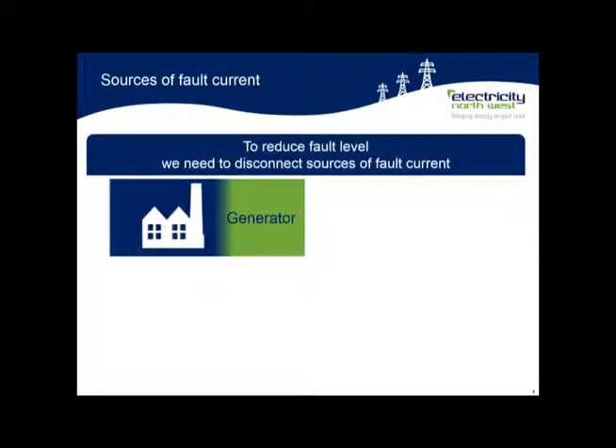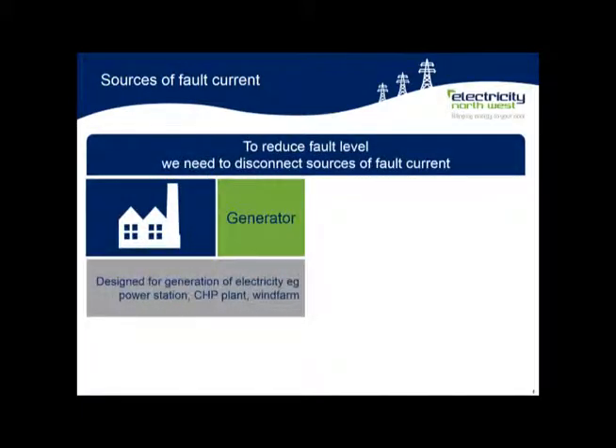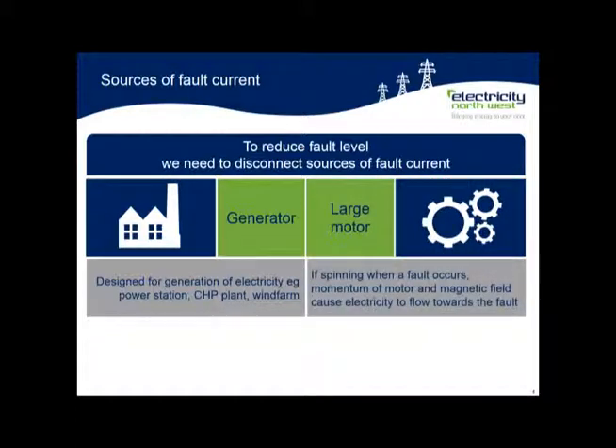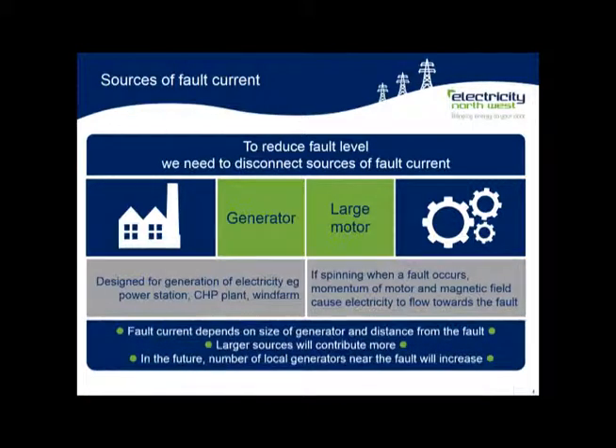To reduce the fault level, we need to reduce the sources of fault current which can be generated. Generators are an obvious source, but motors that usually consume electricity can become generators during a fault. This is because of the natural relationship between electricity, magnetism and motion. The magnitude of the fault current that flows depends upon the size of the generator or motor and the distance away from the point of fault. In the future, as there will be more local generation on our network close to the point of fault, there will be an increase in the potential fault current or fault level, and this is what we need to manage.